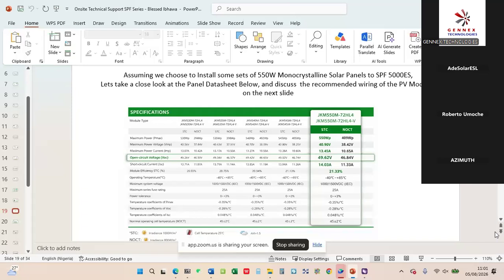During the daytime when there is not much sun, the voltage will be high but the current will be less, and these machines are prone to issues when voltage is high. So it's very important, especially in dull weather - maybe you have a machine installed and the customer says they are getting O3. That O3 is just telling you the voltage is too high, because at that particular time, when the sun is not up yet, the panels give you crazy voltage but low current, and it affects the machine, causing it to report O3. This is just from the design, so please check the data sheet.